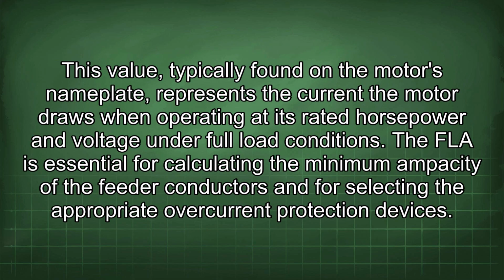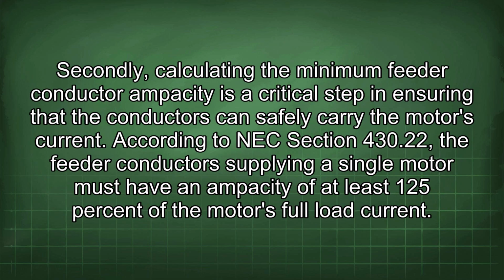This value, typically found on the motor's nameplate, represents the current the motor draws when operating at its rated horsepower and voltage under full load conditions. The FLA is essential for calculating the minimum ampacity of the feeder conductors and for selecting the appropriate overcurrent protection devices.